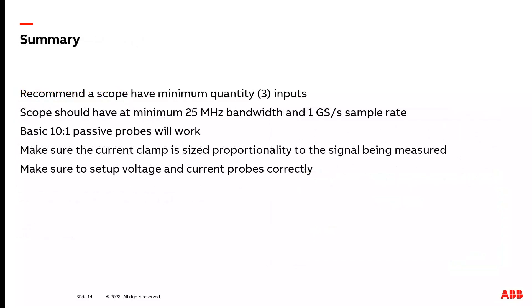Let's summarize what we discussed today. First, I recommend your scope have a minimum of quantity three inputs. This allows you to hook up, for example, three voltage probes all at one time during a lockout-tagout procedure, and then you can see all the individual waveforms in each phase without having to re-lockout-tagout your VFD to move voltage probes. Next, the minimum specifications I recommend your scope have are 25 MHz bandwidth and 1 Giga samples per second sample rate. This will allow you to see the fastest signal normally you'll be trying to check, which is the rise time on an IGBT.